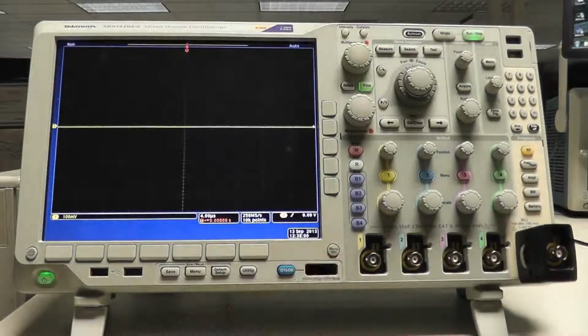The next step is to erase the existing protected user data using the *PUD command from the programmer manual. You can either write the command directly to the instrument using OpenChoice Talker Listener that is included in TekVisa, or you can write the commands into a text file and load it on the scope as a setup file.